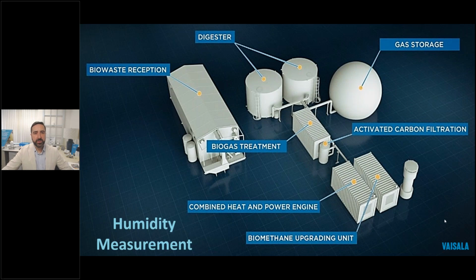But with all my talk about moisture issues, it's time that I bring up actually measuring humidity, which in itself is not a common measurement in biogas systems. And the reason it's not common is because of the difficulty of performing that measurement. H2S and high humidity is going to foul any traditional humidity chip sensor. And that includes any of Vaisala's industry-leading, highest performance polymer sensors with their chemical purge and self-heating functions. They're simply going to become corroded in raw biogas streams.